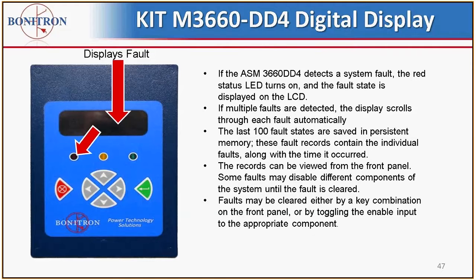The far left indicator is the fault indicator. When it detects a system fault, it turns on, and the fault state will be displayed in the LCD window. If multiple faults are detected, the display scrolls through each fault automatically. It says 100, but actually now we only provide 30 fault states. The equipment doesn't fail that much, so it never gets to 100. They'll be saved into persistent memory, so in other words, you can go back and review the faults and the different parameters that the faults indicated at a later date. Faults can be cleared either by a key combination on the front panel or by toggling the enable input to the appropriate component.